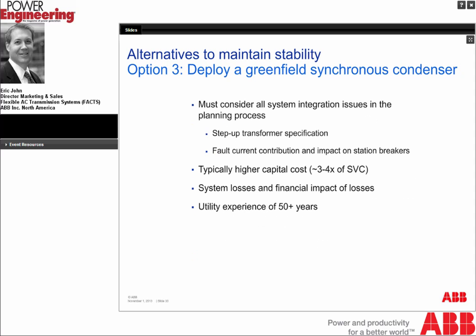The third alternative is to deploy a Greenfield synchronous condenser. And some similar considerations as you had for the conversion, although there are a couple of technical differences. One is that the new synchronous condenser requires its own step-up transformer if it's compensating a transmission system. And the transformer for that unit is going to be kind of a special animal. If you are running a transformer with very high VAR loads on it, the transformer can be driven into saturation if it's a conventional transformer. So the transformer needs to be specified properly so that the secondary voltage is correct and that it's not driven into saturation when you load it with VARs.